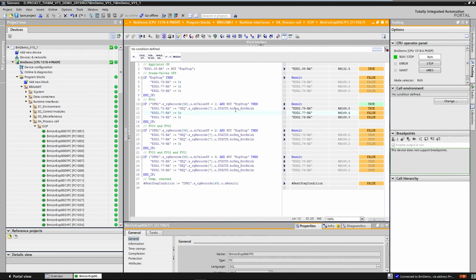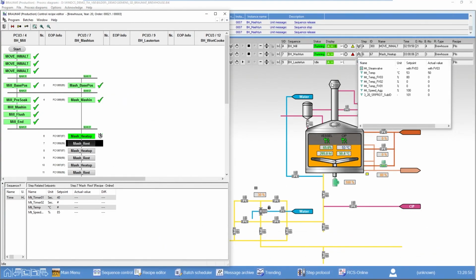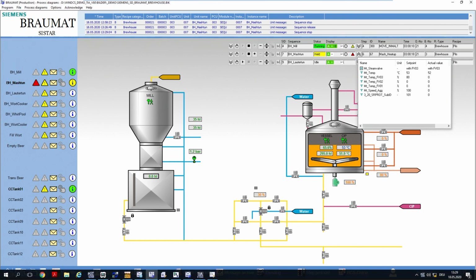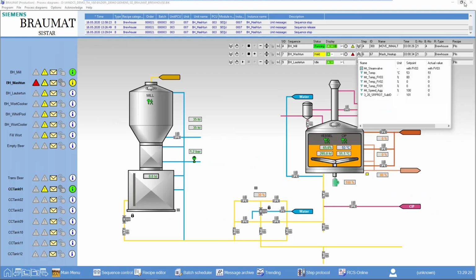Including the connection with an attribute on the unit, namely the hold attribute, we can implement a further interlock here. I.e. always, and now please note the difference, agitator, valve, whenever I set the subsystem to hold, the corresponding steam valve is deactivated, but the agitator remains active. That is this command up here. The last command within a step is always the step on condition. We link this to another attribute. And this attribute is 1. It is true when the actual temperature value and the set point value match.